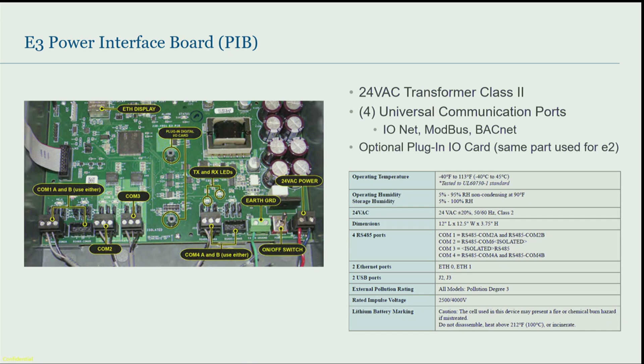Communication lights, the termination jumpers. You can plug in a digital I/O card just like you could with the E2, and it's actually the same part you had on the E2. You've got an Ethernet display, Ethernet port on the top left that connects to the port on the door. But like I said, everything is just the same earth ground, same power connection that you have. So when you're changing out an E3 versus an E2, just pull your plug wires off, your power wire off, pull the controller off, plug in the same ports.